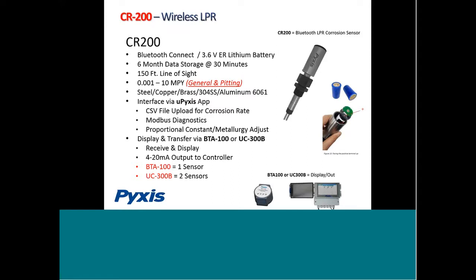We say 150 feet line of sight, but in reality we've got data showing 300 feet line of sight, and that's the same technology in our tank level monitor. And again, the measurement of detection is 0.001 MPY to 10 MPY. Each metallurgy has a different scale with a lower detect limit of 0.001, but for example, copper has an upper of 2.0 MPY. Now, we offer both general and pitting. The pitting is on a scale of 0.001 or 0.01 to 100 MPY. And it will interface via the Pyxis app, same app that I just talked about for the level sensor.